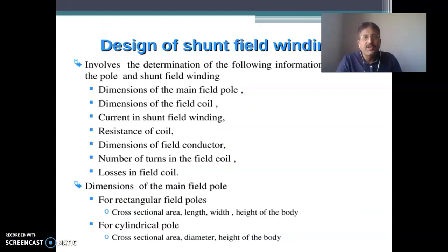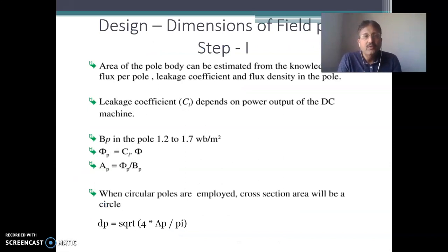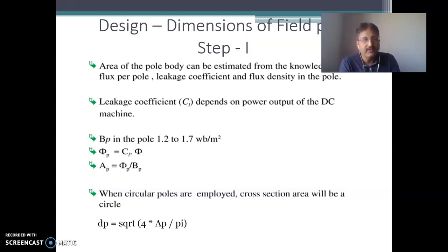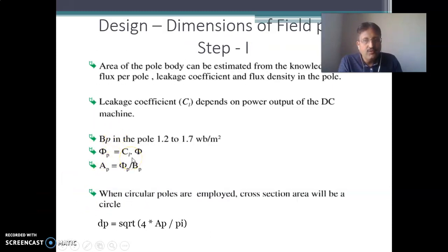The first step is the design of the field pole — finding the dimensions. To find out the area of the pole body, you need to find out the flux required in the DC machine. The working flux is determined from the voltage required, power output, and torque output. Once the flux is decided, consider the leakage coefficient and find out the flux per pole: phi_p = leakage coefficient × flux. Then assume the flux density in the pole in the range of 1.2 to 1.7 Tesla.